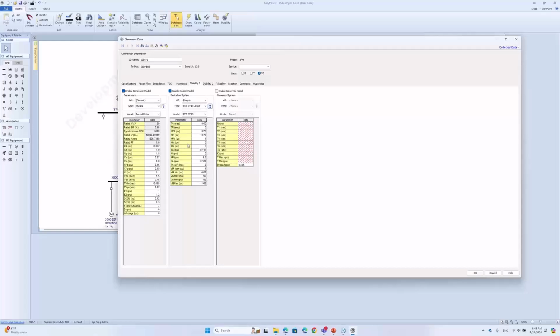We have the AC excitation system, which uses alternating current as your excitation system, right? Which is faster and widely used. And at last, we have the static excitation system, which is used in those power electronic devices, which is extremely fast and extremely powerful, but maybe more expensive to implement in your system.